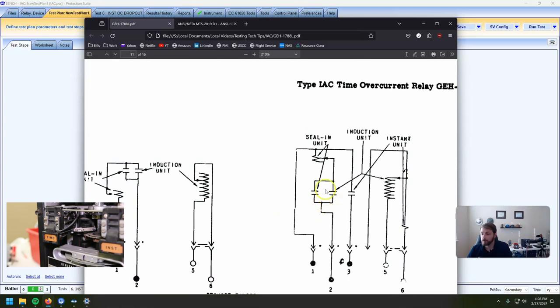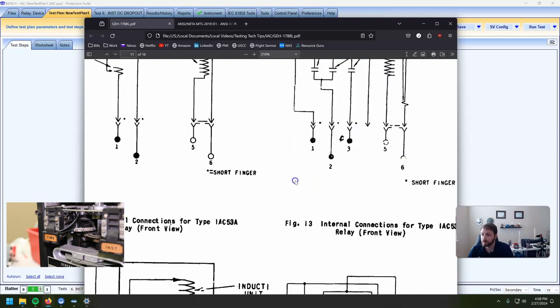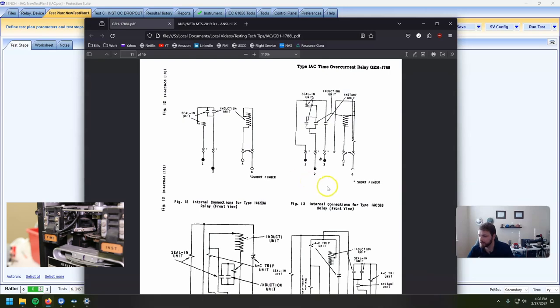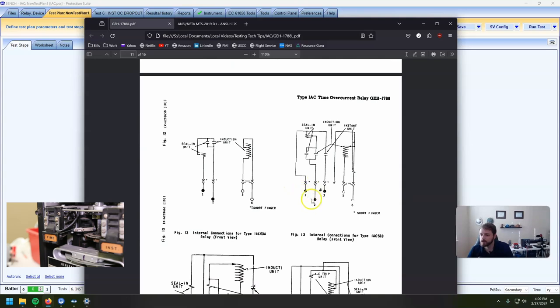The instantaneous unit doesn't have a seal-in — it's just the time over current induction unit. Between terminals one and two there's this little coil, which runs on DC tripping current, not the AC from the CTs. It's actually the DC tripping current to your trip circuit. They'll totally work on AC, but we test them on DC. I've got a DC current source hooked up between terminals one and two from my test set.